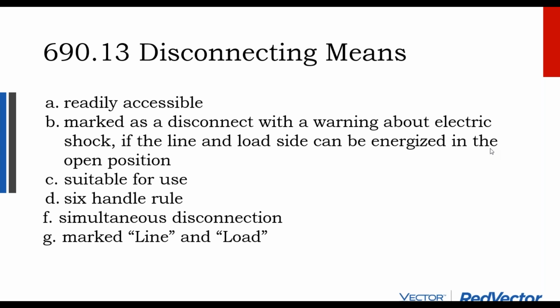It needs to be labeled. And there's this 6-handle rule that applies to it. Basically, your service panels have the 6-handle rule too. Basically anything needs to be able to be de-energized by flicking no more than 6 handles. So once you have more than 6 inverters on a service panel, you need a main breaker, an external disconnect switch, more of a general code requirement. Simultaneous disconnection: it needs to disconnect both the positive and negative at the same time. It needs to be marked line and load.